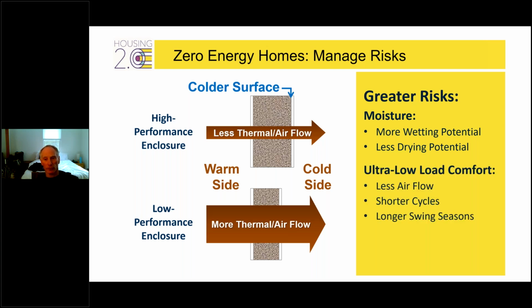The next thing to manage risk is we have to recognize we have ultra low load homes. So comfort completely changes and is more risky. Historically, we've not been very diligent about our thermal distribution system for heating and cooling. Now that we create even dramatically lower airflow, will we have good mixing and comfort throughout the home when historically we don't address really good duct delivery systems? The other two have to do with moisture and comfort.